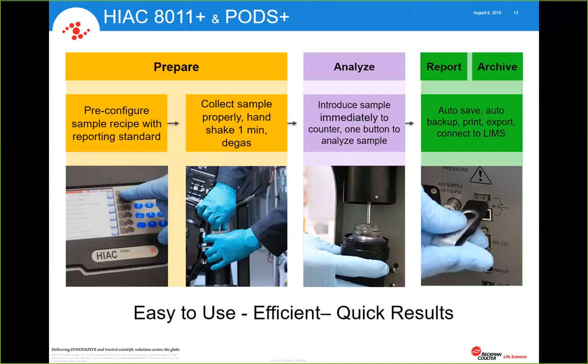Again, as far as the simplicity of using the instrument, as always, preparing the sample fluid before you actually analyze it is the #1 contributor to good, repeatable, and accurate results, or faulty results. If you're not preparing your sample properly, then you're basically introducing error right into the analysis. So it's very fundamental.